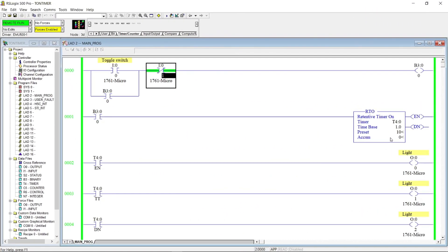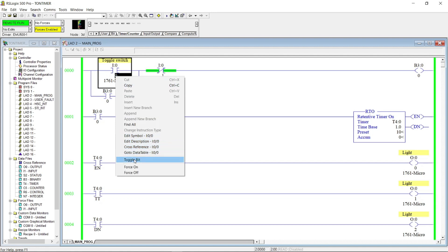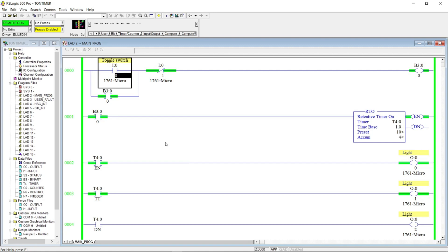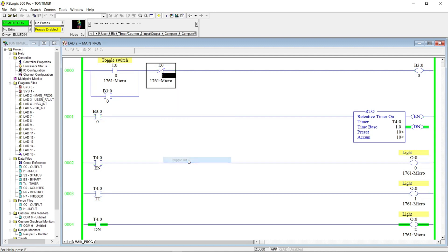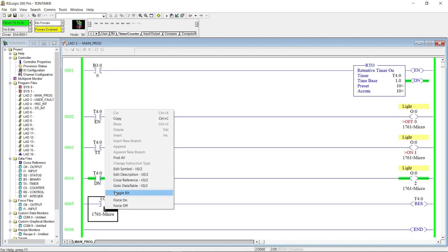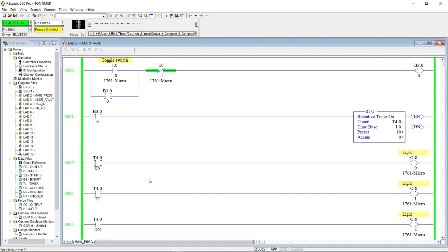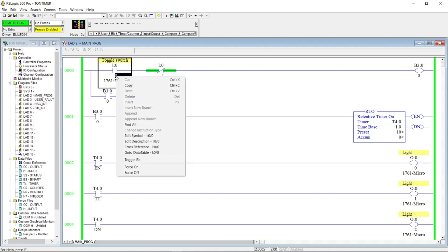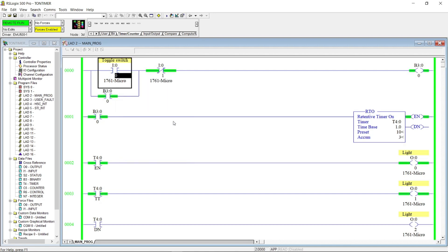The Retentive Timer On counts time base intervals when the instruction or input is true, and retains the accumulated value when the instruction goes false or when cutting off power supply. We have to reset the timer T4:0, so we will put a reset instruction in the program. When the accumulated value reaches 10 seconds, it will not reset even if you cut power with the stop button. Unlike the TON instruction, which automatically resets the accumulated time upon a transition from high to low, the RTO will simply pause the accumulated value during this transition. In other words, the timer retains the value it currently has until it is energized again or forced to reset.